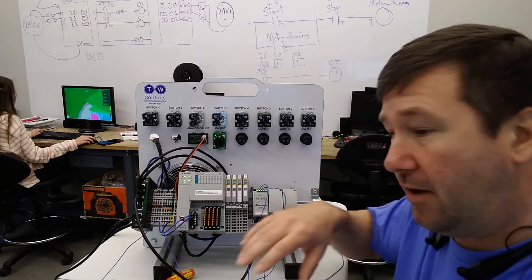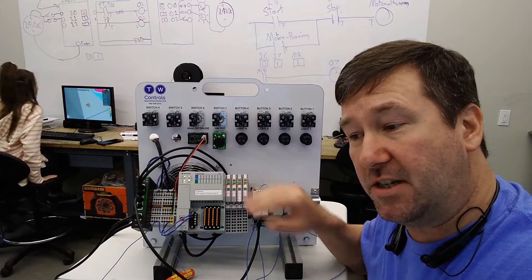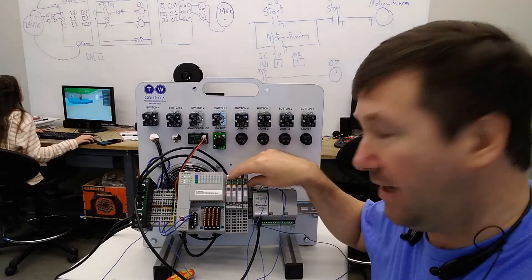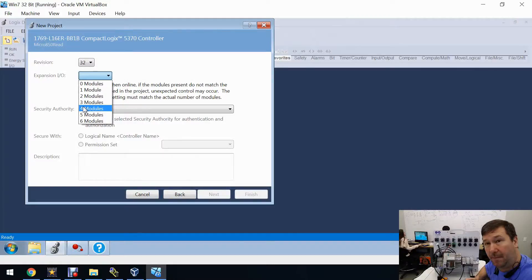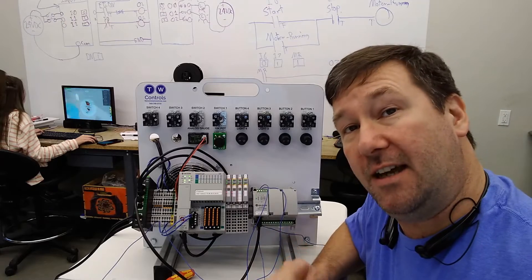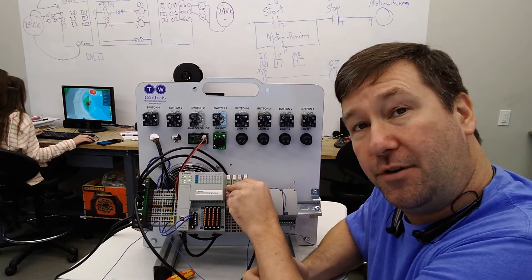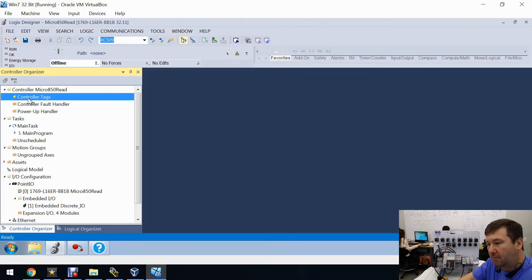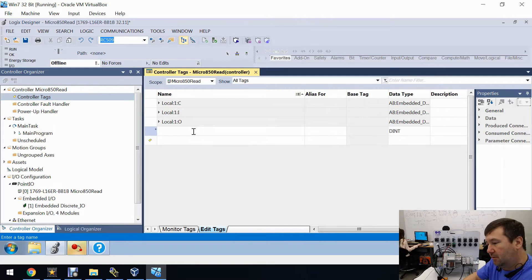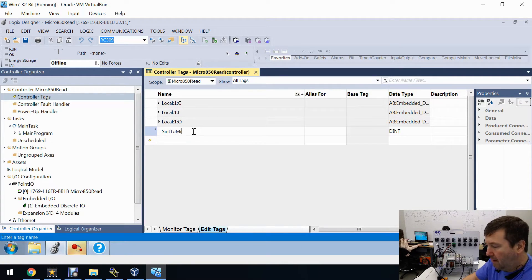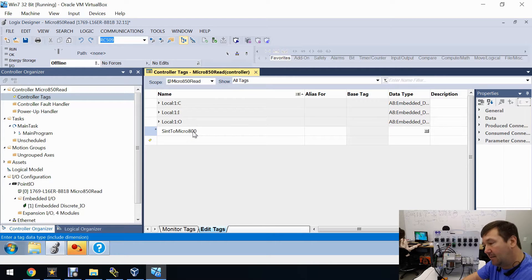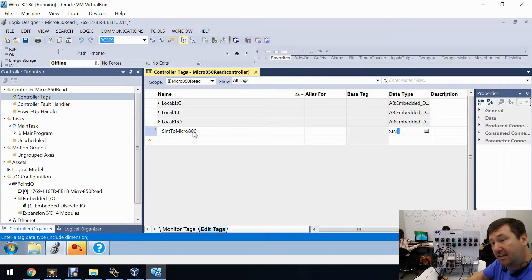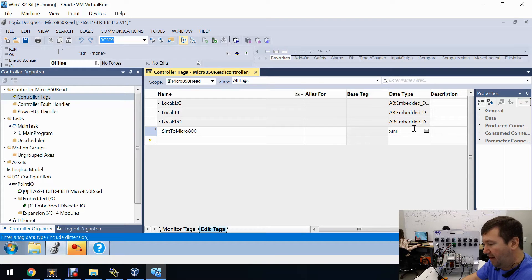If you're using one of our trainers, your expansion IO will typically be set to zero. I've got some modules for other videos so I'm setting mine to four. You need to have that set correctly — if you put the wrong number your processor will fault when you try to go into run mode. We're going to create two controller tags: first, 'SintToMicro800' as a SINT (single integer) array of 20.